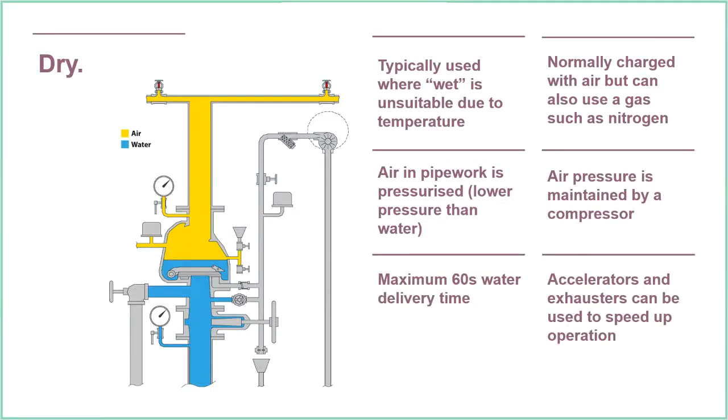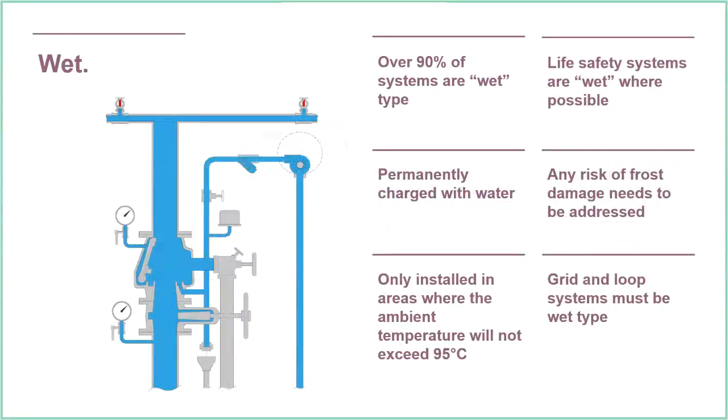The air is maintained. So again, with the wet system, that's something I didn't mention actually about a jockey pump. On a wet system, we use a jockey pump to maintain pressure within the pipe above the alarm valve, and below, to be honest. But mainly it's there for the pipe work above. We're going to get small leaks, and because water doesn't compress very easily, a small leak causes quite a large drop in pressure. So we have that jockey pump there just to top it up.